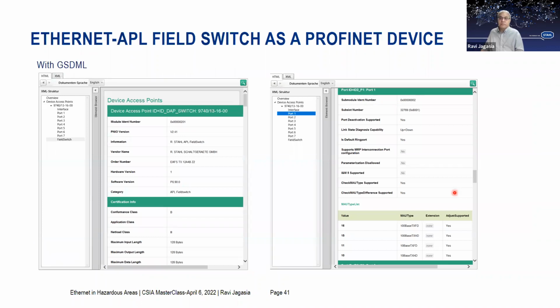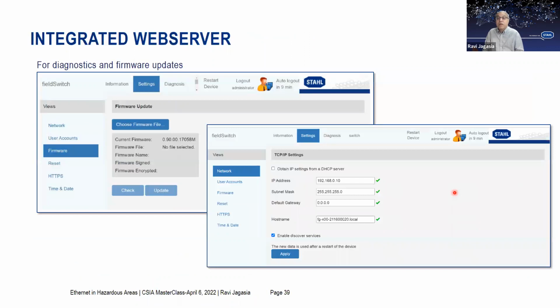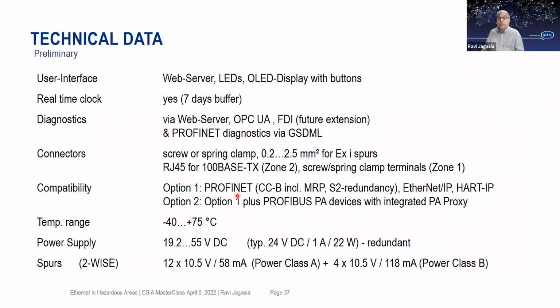And as I mentioned earlier, what about the field device or the Ethernet switch, where we talked about an option with Profinet or Profibus PA. Basically, if I have a Profibus PA device instead of an Ethernet-APL device, the field switch can act as a proxy, convert the Profibus PA into a Profinet protocol, and then your backbone running into your control room will be Profinet based, or it can also be Ethernet IP based, or it can also be HART IP based.